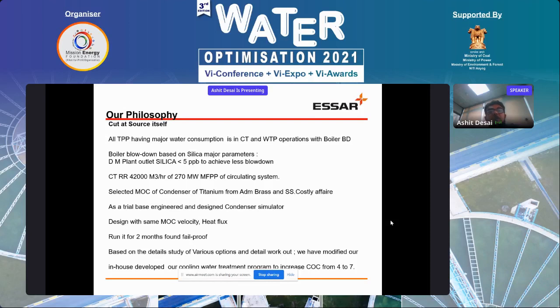Now, if you talk about boiler water blowdown, silica is the major component for deciding the boiler water blowdown quantity. What we have decided is that we will improve and give the best quality water to the boiler, so that our blowdown will be less. We are maintaining less than 5 ppb of silica at any point of time at the DM plant outlet, so that boiler blowdown can be minimized. Whatever boiler blowdown is generated is less than 1% basically.